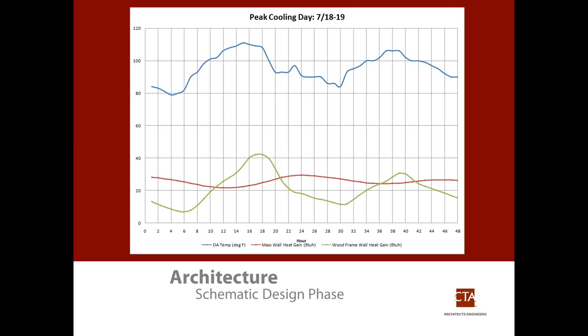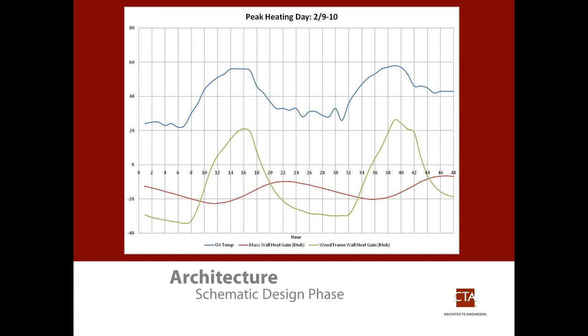Now we can start looking at night flushing and clearing some of that out. So it looks like a good deal from the cooling standpoint, but let's look at heating. Same issue here, except we're looking at the valley: the minimum temperature happens overnight at 6, 7 o'clock in the morning, and doesn't hit the building until about noon. But at noon your building is full, and you're going to have to start heating to make up for that. On this particular project, we actually had more heating degree days than cooling degree days. We found it was more or less washed out with the thermal mass in there. But there are some cases where you have a lot of cooling load, where maybe that's a good idea.